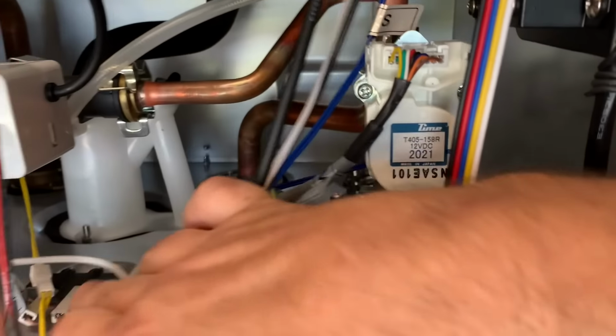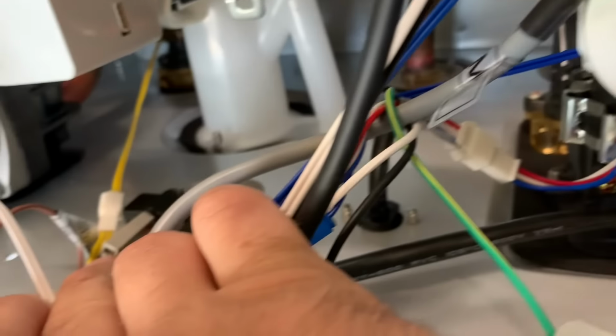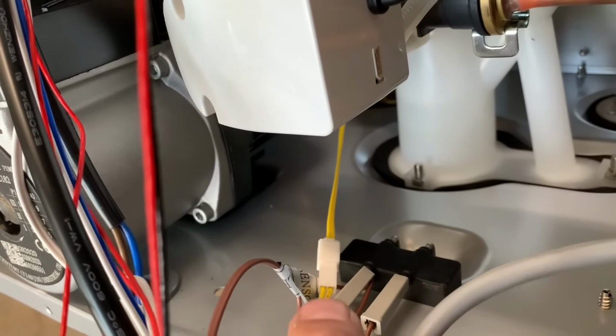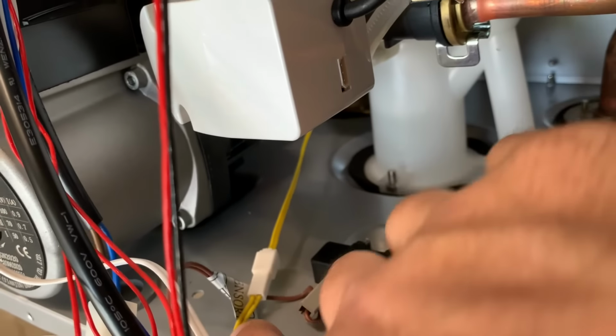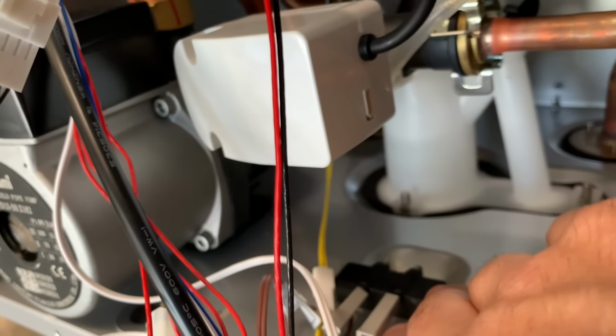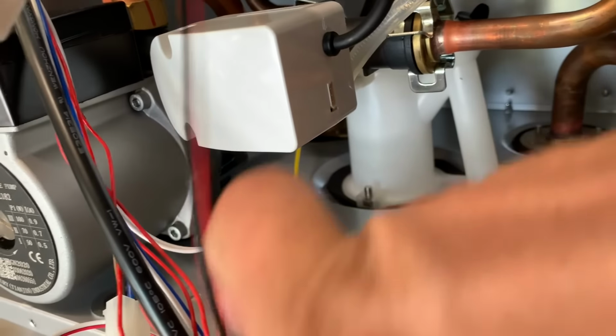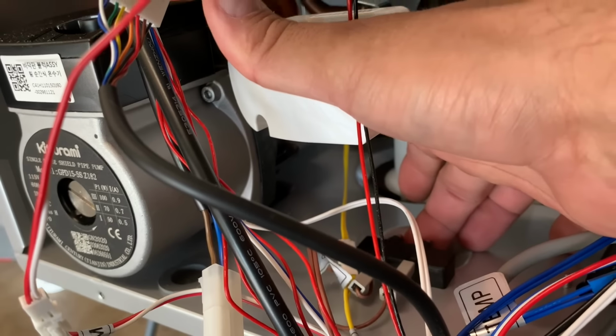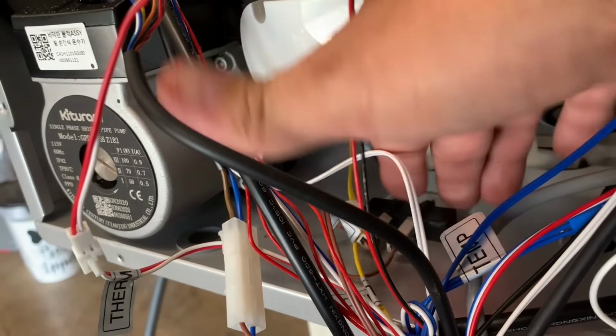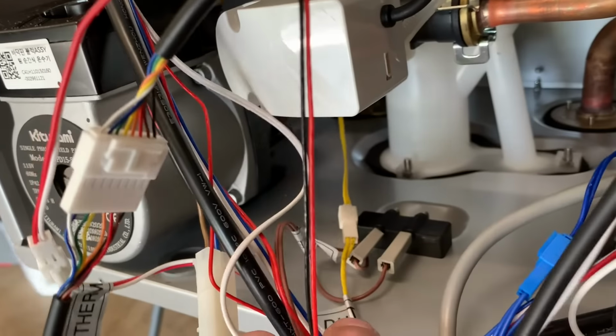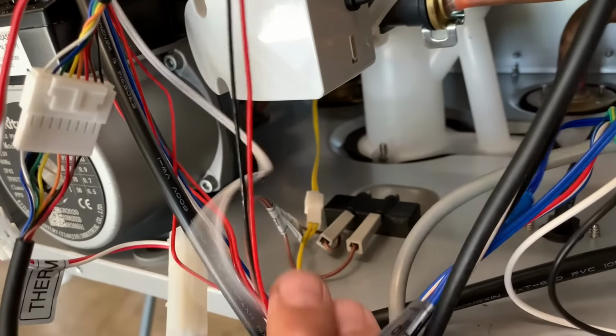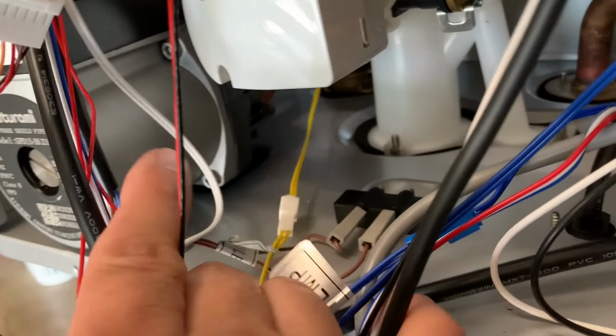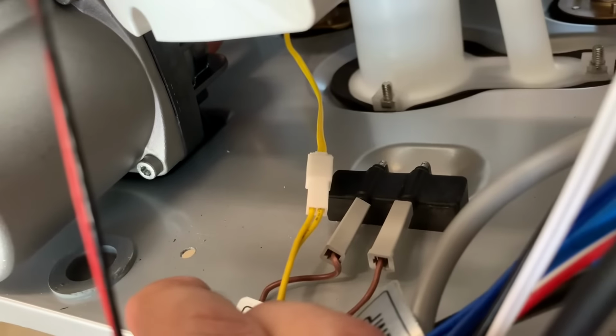and this plate, this is the water sensor right down here. Water leaks inside of the unit, internal leak, condensation, vent leak, whatever the case may be, water's getting in here somehow. It'll pool right here and connect and close this circuit and throw the code. So to check this, you almost need to remove this power control board and that plate, and then you can get a really good look back there.